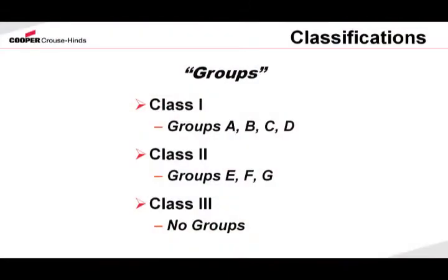To further break it down into a little bit more of a science, we get into group designations. For Class 1 gases, vapors, and liquids, we have Groups A, B, C, and D. The only member of Group A would be acetylene. For Group B, we have hydrogen and hydrogen-based gases. For Group C, we would have ethylene. And for Group D, we would have the hydrocarbon type gases. For Class 2 locations, we have Groups E, F, and G. Group E would be metallic dust. Group F would be carbonaceous dust. Group G would be grain dust. There are no group designations for Class 3 flyings and fibers locations.